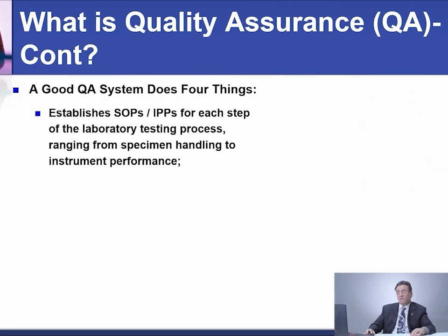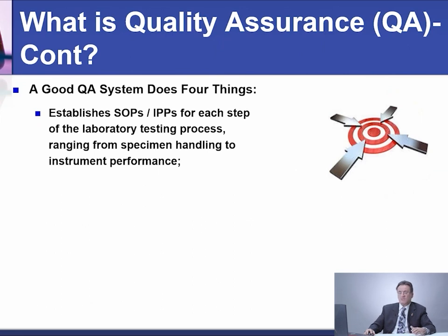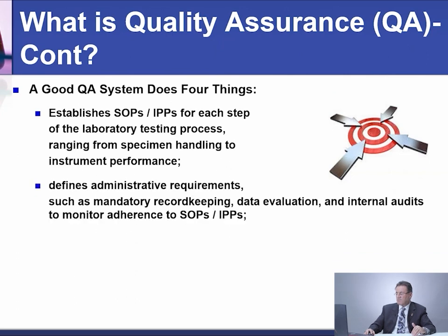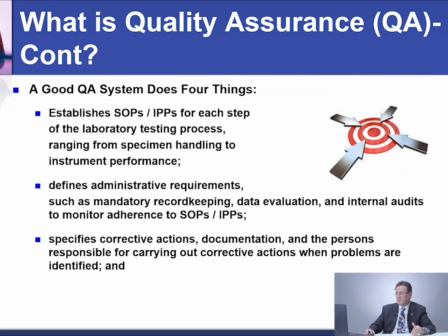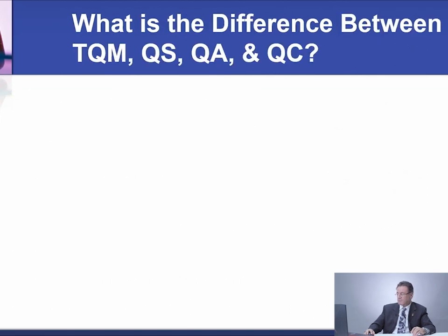A good quality assurance system does four things. First, establish SOPs — Standard Operating Procedures — also known as IPPs or Internal Policy Procedures — for each step of the laboratory testing process, ranging from specimen handling to instrument performance. Second, define administrative requirements such as mandatory recording, data evaluation, and internal audit to monitor adherence to the SOPs. Third, specify corrective action documentation and personnel responsible for carrying out corrective actions when problems are identified. And finally, sustain high quality employee performance.